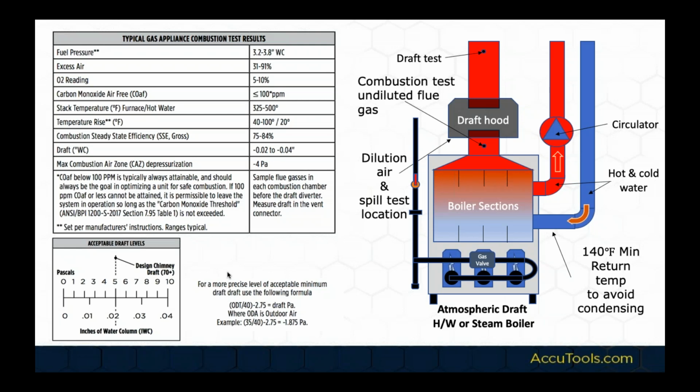And just like a gas furnace, we need to make sure that we have correct input. And a lot of times on boilers, you have to periodically pull off what's called the bonnet on the top and clean between the cells, brush between the cells, because the deposits of rust and gas on there will slow down our excess air. And when you have high CO on a boiler, typically it needs cleaned. That's a very typical problem. We want to see about a 20 degree temperature rise on the water going through a boiler when it's set up. It's very, very typical, but follow manufacturer's directions on there.